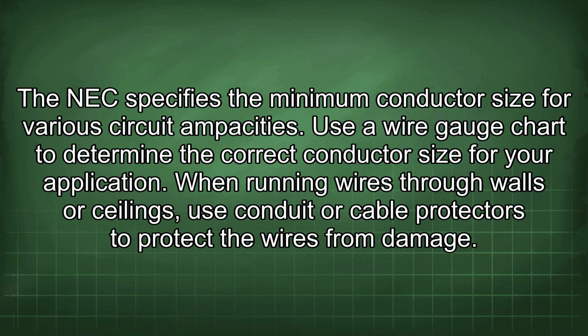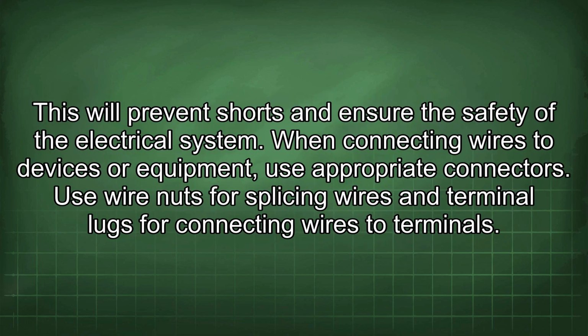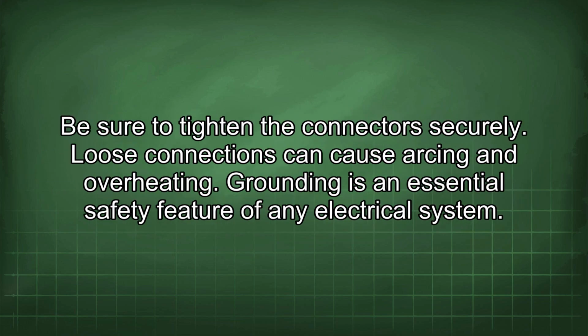When running wires through walls or ceilings, use conduit or cable protectors to protect the wires from damage. This will prevent shorts and ensure the safety of the electrical system. When connecting wires to devices or equipment, use appropriate connectors. Use wire nuts for splicing wires and terminal lugs for connecting wires to terminals. Be sure to tighten the connectors securely. Loose connections can cause arcing and overheating.